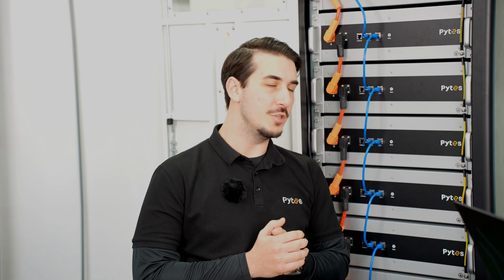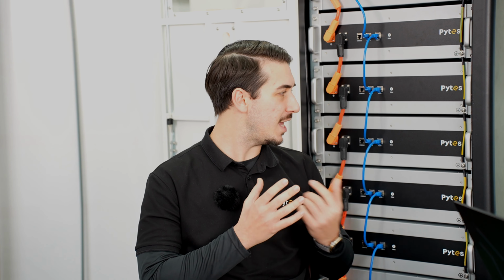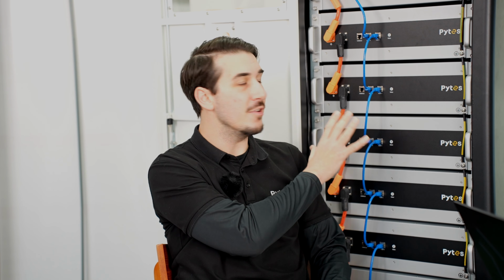The second thing installers should double check before installation is things like wire runs, the height of the cabinet, and the total weight of the cabinet. Most of our high voltage indoor solutions come with all the cables, connectors, and everything needed to put the batteries together in the cabinet, like you see behind me, and to connect it to your inverter. Those pre-made cables are a certain length, so make sure they'll work for your install. If not, contact us and we can help you work out custom cables or get you the right connectors.